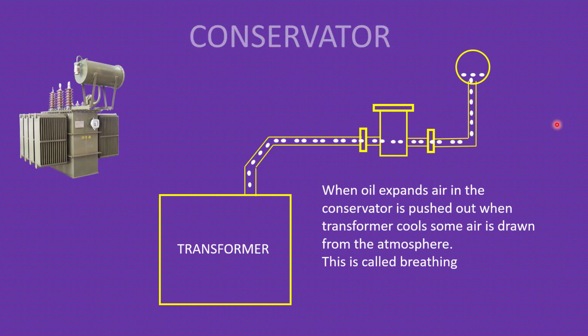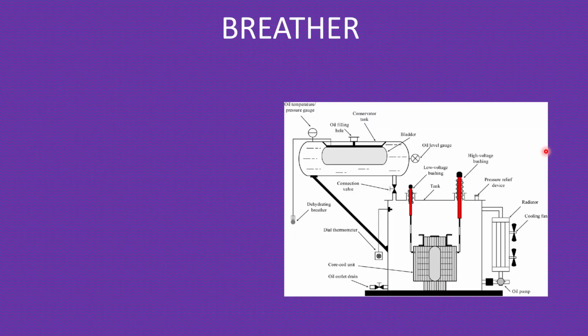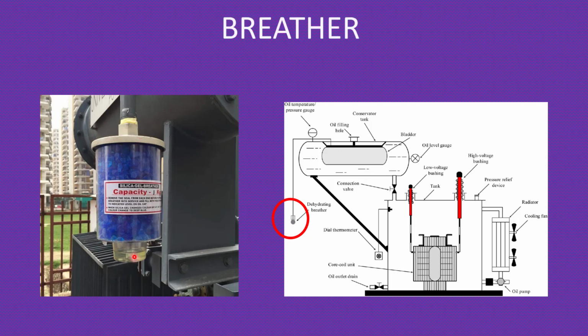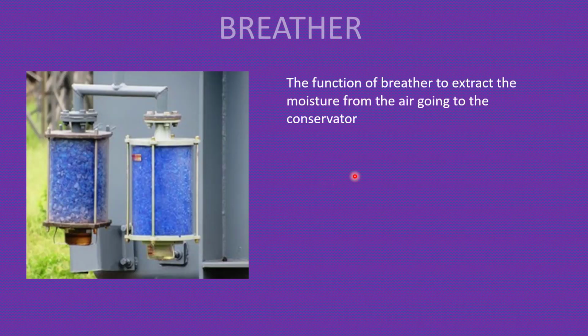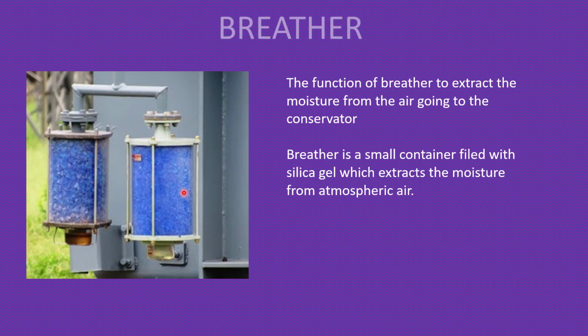As we said earlier, the transformer oil should not be in contact with moist air. The air should not contain any moisture. For this purpose, we are using a mechanism. You may have seen this with the transformer. It is attached to the conservator. This arrangement is called a breather. You can see this is an enlarged picture of a breather. The function of the breather is to extract the moisture from air going to the conservator. The air goes to the conservator through the breather, so the breather extracts the moisture from the air. You can see these blue crystals, right? This crystal is a silica gel crystal. So a breather is a small container filled with silica gel which extracts the moisture from atmospheric air. The condition of the silica gel in the breather has to be periodically inspected and taken care of.